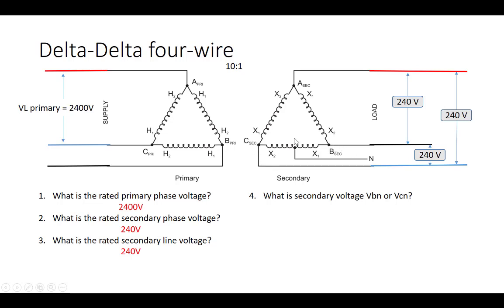Now again, we have on the secondary a single phase supply between B, C, and the center tap we have here. So if this is 240 volts, phase B to C voltage, and we have a tap right in the center, the voltage from B to that point will be half that voltage, 120 volts. And the voltage from C to that center tap will be 120 volts as well. The one voltage that's left that we can see on the secondary is a voltage from A to that center point. This is called our high leg voltage and can be a little difficult to calculate. The next slide will give us a hand understanding how that would work.